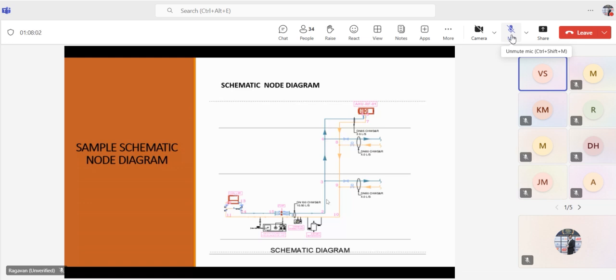Some of the contractors, what they will do is take the IFC drawing and put it in their title block, and then they will assign similar node numbers and present their head loss calculation. But the real issue is in the coordination time. During coordination, there are ups and downs that will come. So that is very important.